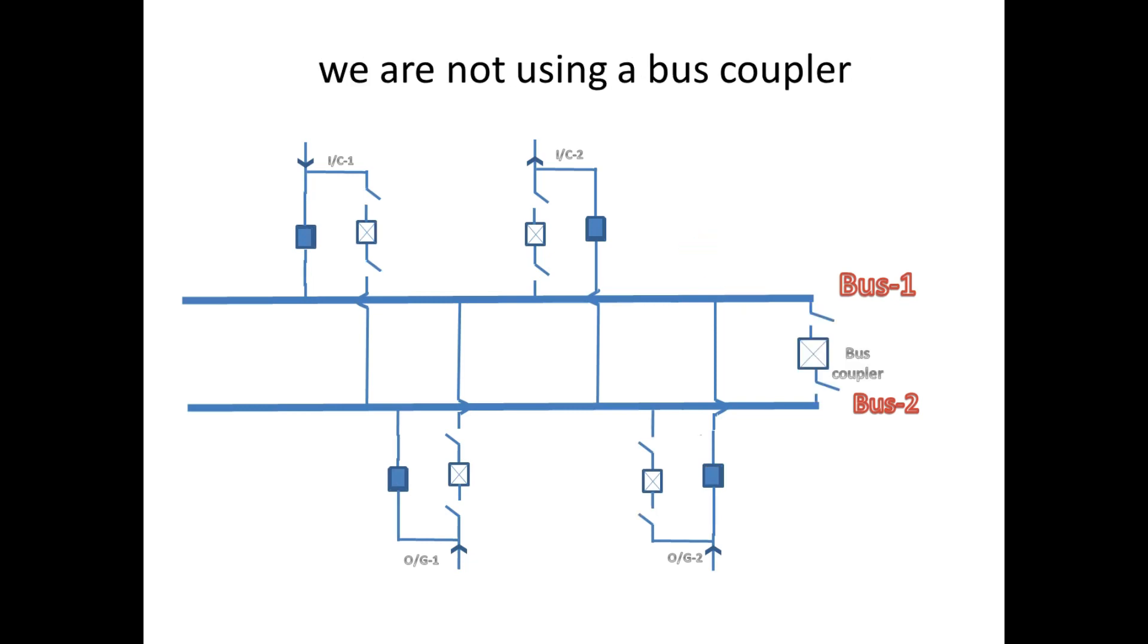Second, if we use a bus coupler, the power supply changeover will take more time due to bus coupler CB closing time and feeder CB closing time. But here we are not using a bus coupler, so there will not be much delay in power supply while closing the circuit breaker to transfer load from one bus to the other.